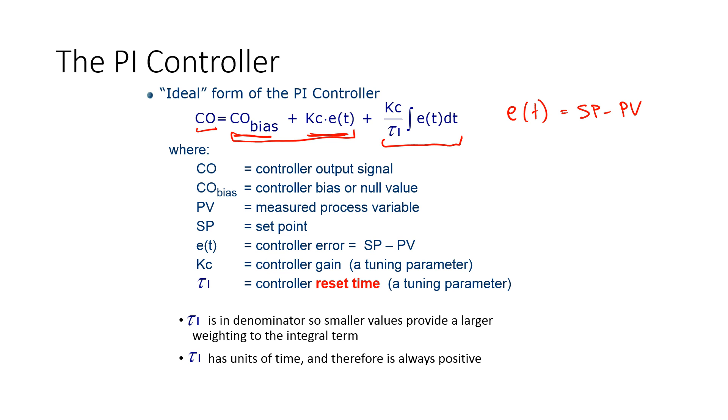Now we're going to be adding an integral term as well. It's going to integrate this error over time and add or subtract a certain amount from the controller output based on the integrated time. We're going to add a new time constant, tau sub i, and that is in the denominator. So smaller values provide a larger weighting to this overall integral term. It also has units of time, and therefore it's always positive.